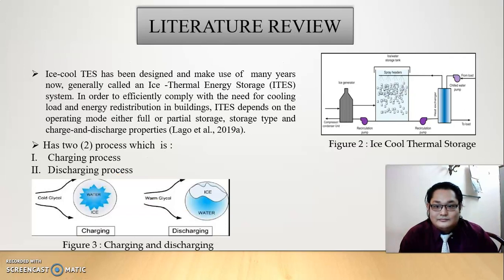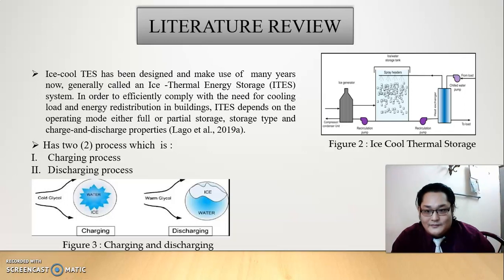Literature review. Ice-cooled thermal energy storage has been designed and used for many years now, generally called an ice thermal energy storage (ITES) system, in order to efficiently comply with the need for cooling load and energy redistribution in buildings. ITES depends on the operating mode, either full or partial storage, storage type, and also charge and discharge properties. It has 2 processes, which are the charging process and the discharging process.